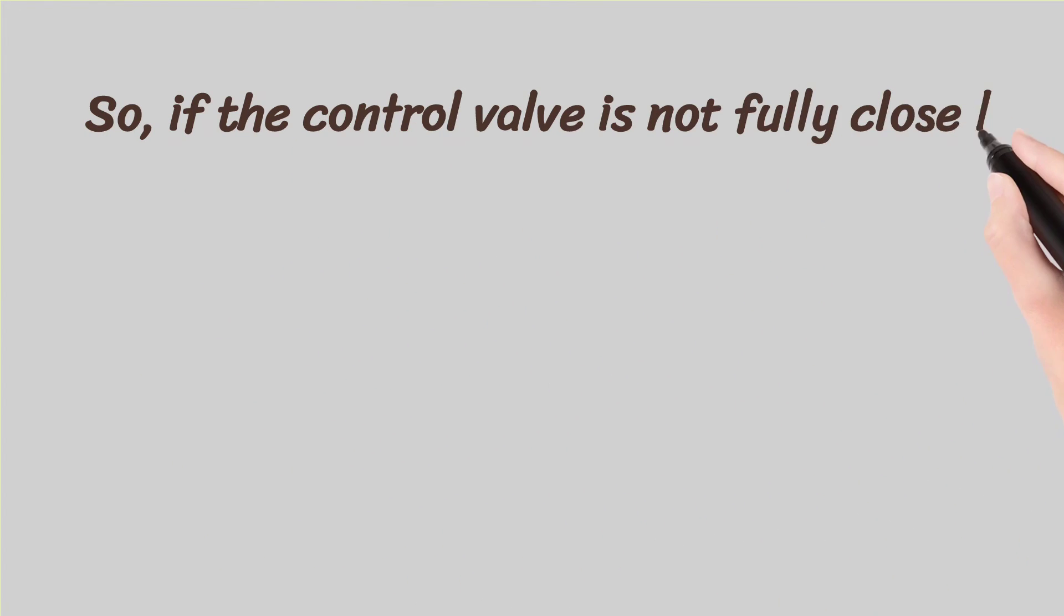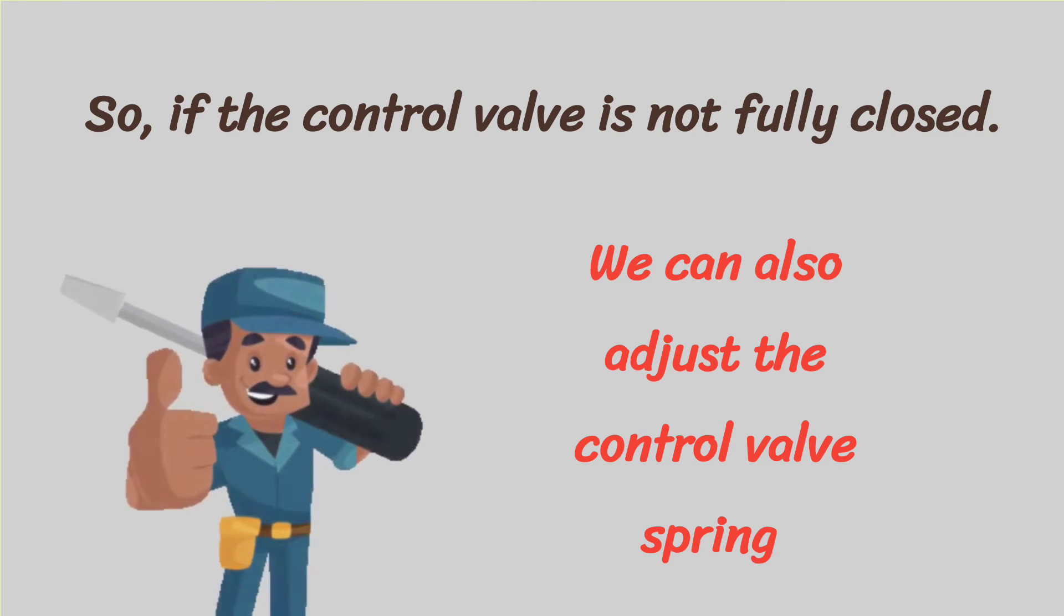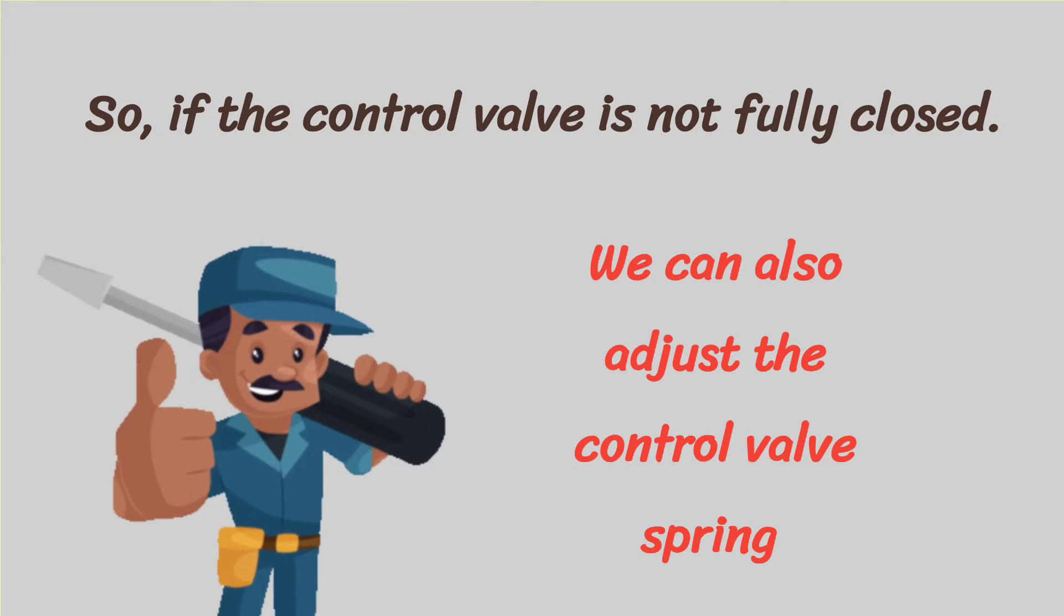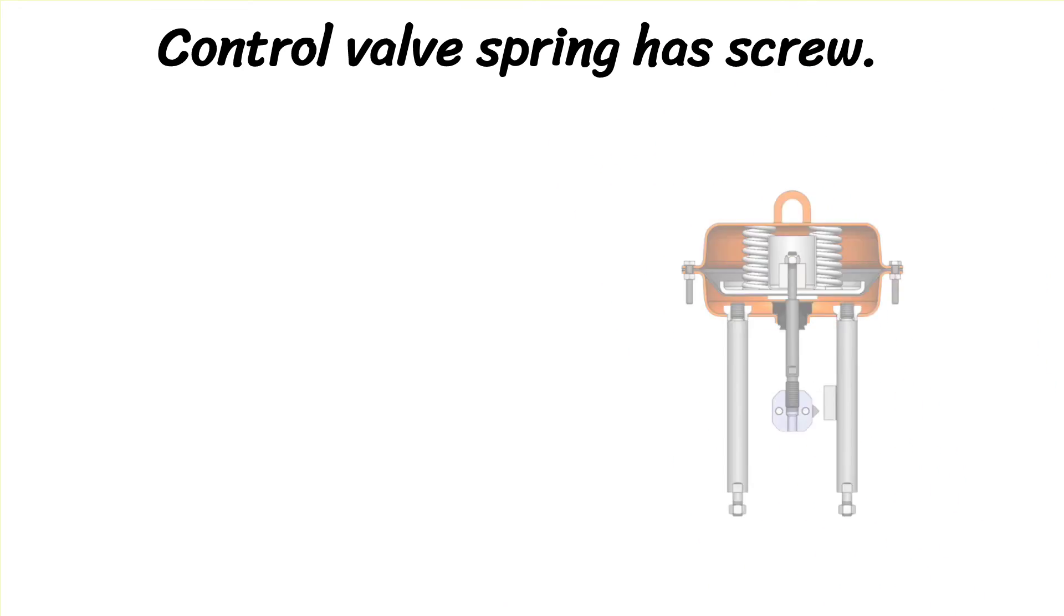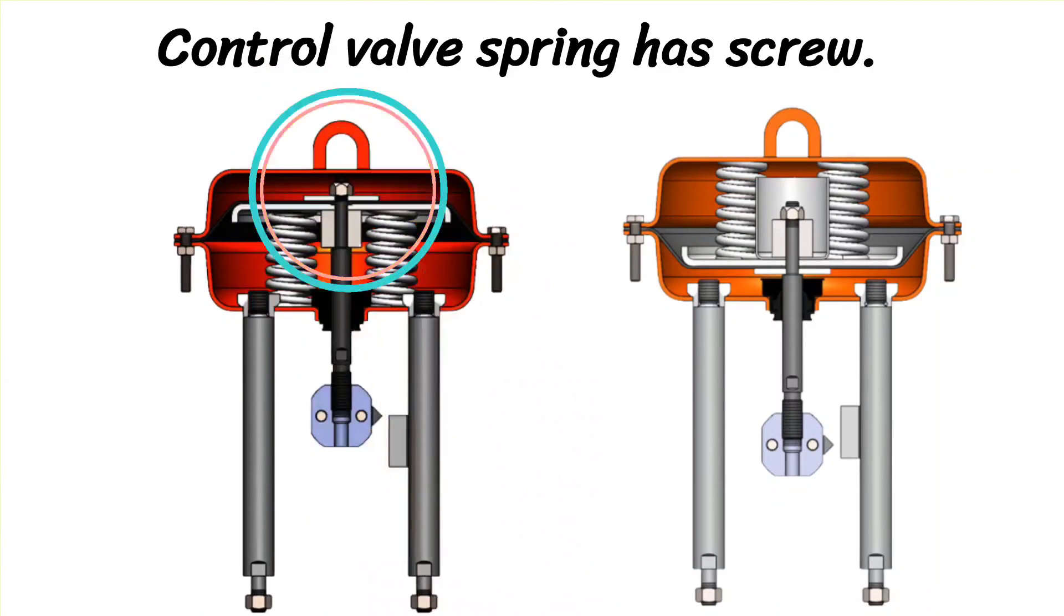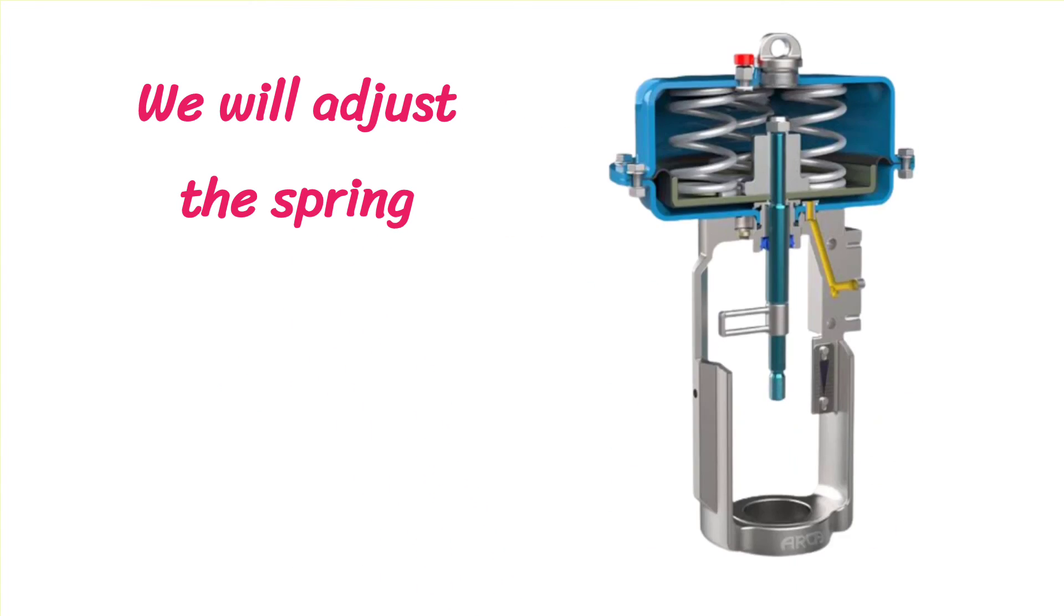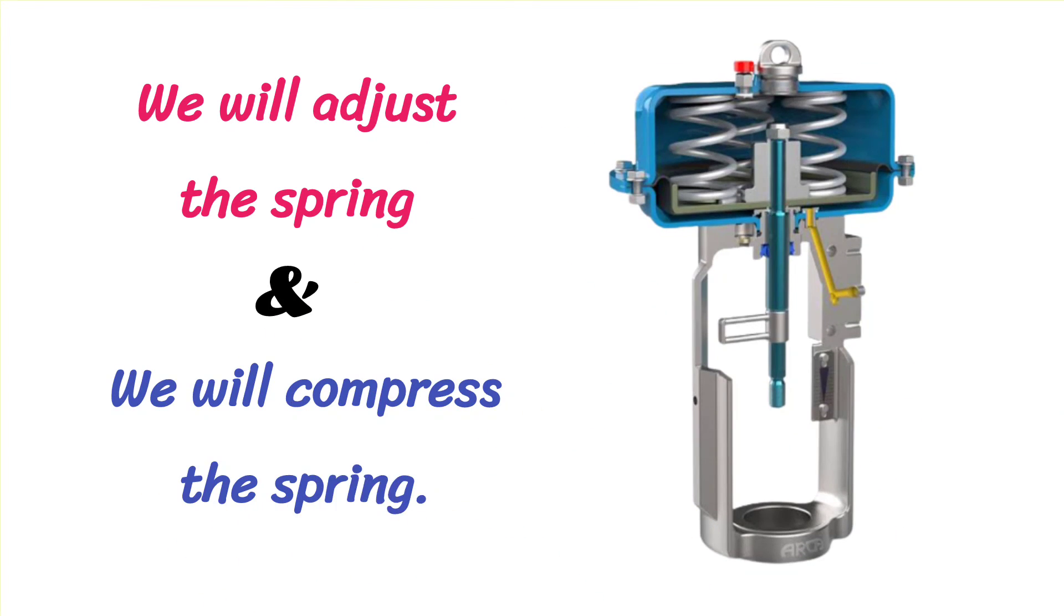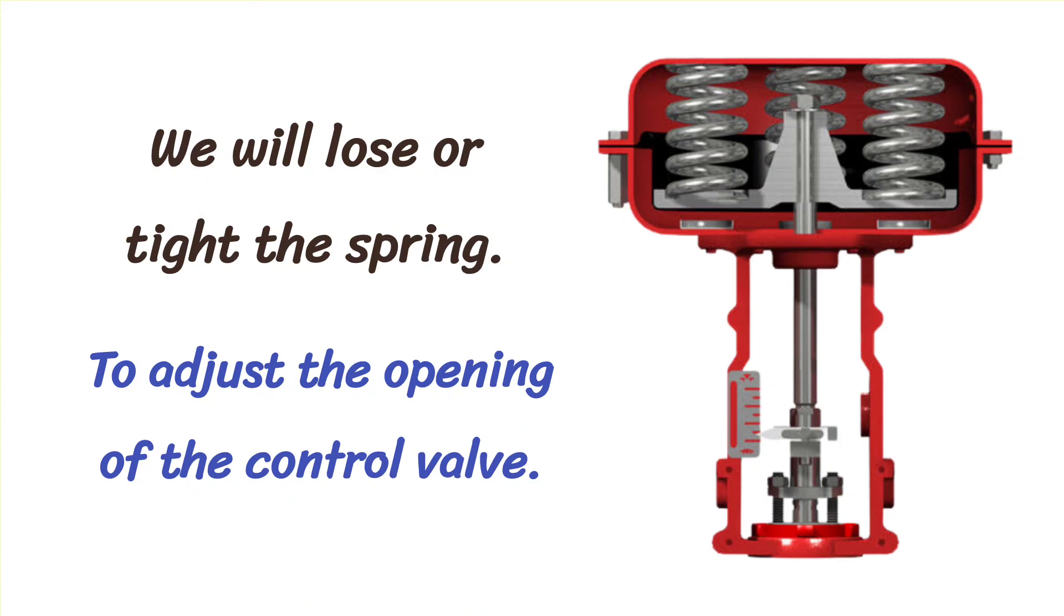So, if the control valve is not fully closed, we can also adjust the control valve opening by spring adjustment. Control valve spring has screw. You can see the screw by the circle shown in the left and right images. We will adjust the spring. We will compress the spring. We will loose or tight the spring to adjust the opening of the pneumatic control valve.